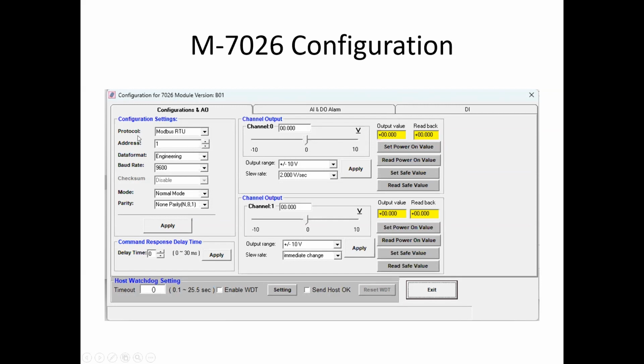For Modbus RTU, each individual device must have its own address. So you can have address 1 for this, then address 2, address 3, all the way up to 255 for this Modbus RTU bus. If you want to add multiple buses or COM ports, for instance, you can add more slaves, or if you have Modbus TCP, they're more versatile and you can have a lot more slave devices and faster communication. I actually prefer Modbus TCP because you can also use the existing Ethernet infrastructure of a building. You can use standard switches.